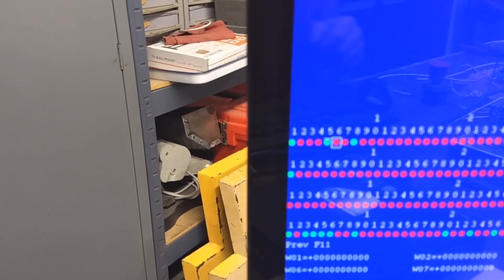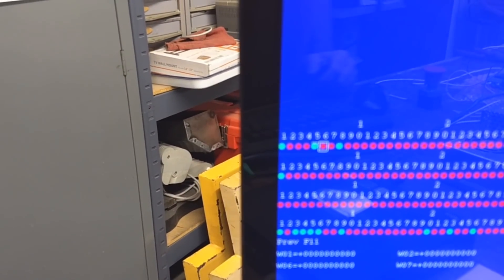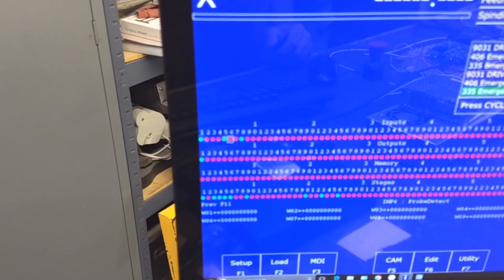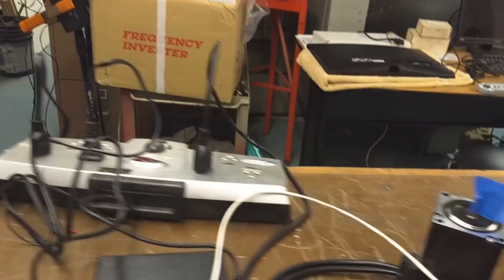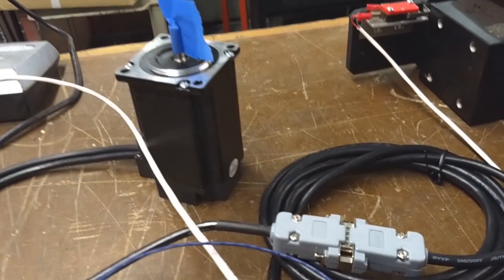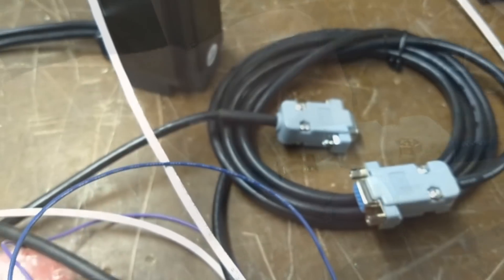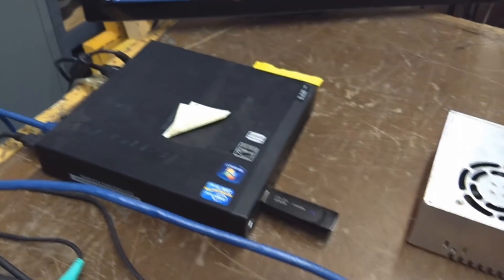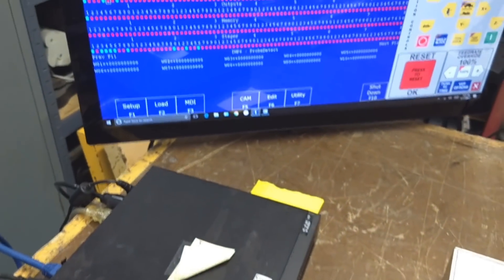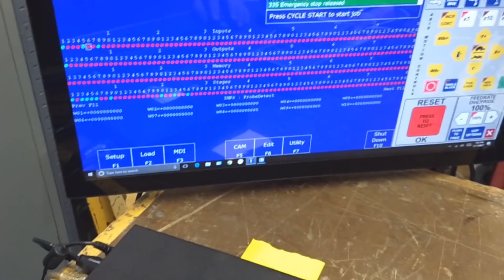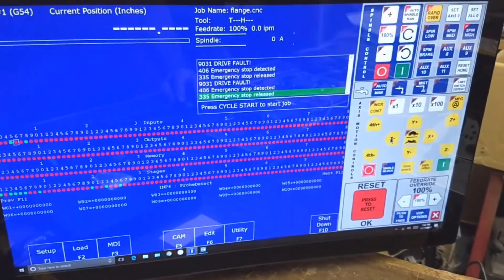So what I'm going to do now is I'm going to create a fault by disconnecting the encoder cable to the drive. Okay, so the encoder is disconnected. So now I'm going to go ahead and try and run the drive.